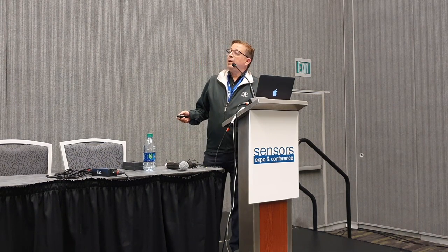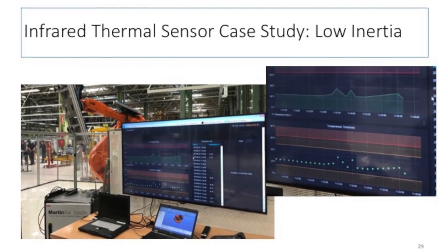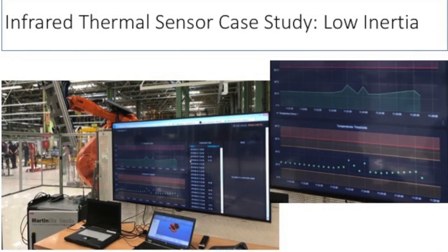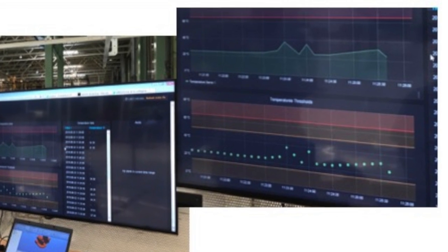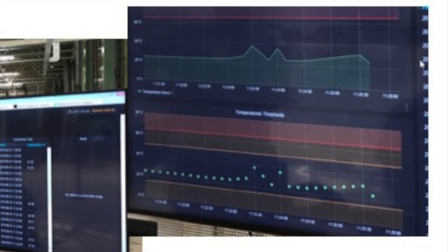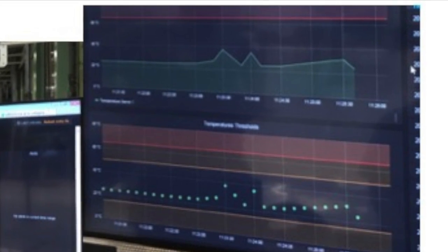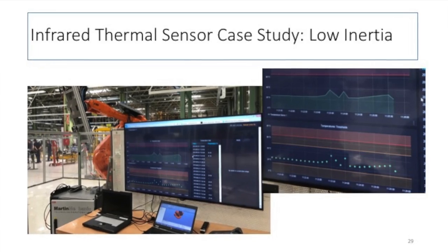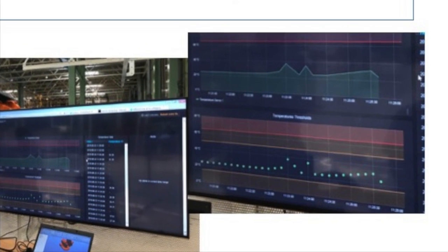And this is a case with robotics, and we have made a zoom-in image over there, and you can see here the peaks of one of the servos on that robot working. You see in the peaks, this is the one process, one movement. You can see each movement of this robot with this kind of low inertia sensors. So again, modern thermopiles and modern imaging sensors can provide by infrared analysis a much better, much faster reading, and with time synchronization with the sensor fusion technology, you can actually allocate each temperature peak with other peaks of vibration or some other sort of stray energy, and then create a model with that.